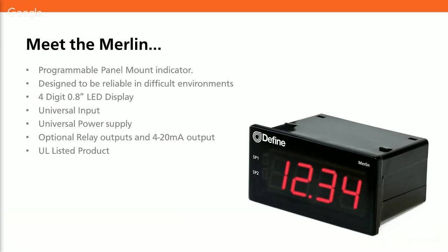So this is the Merlin. As you can see, it's a small panel mount indicator. It's very flexible, and we've designed it to be used in an industrial environment. It has a 4-digit LED display with configurable decimal point options, and you can programmably change the scaling for the display as well. The display can be easily configured to show a scaled version of the input signal. So that means you can show a value that is more meaningful for you in your process. So rather than showing raw voltage, for example, you can show temperature or flow rate in liters per minute.